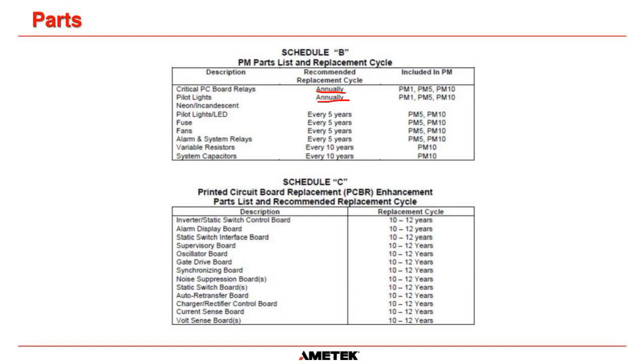Any pilot lights. On our DPPs, we've gone away from pilot lights. So on our oldest systems, we will replace the lamps and the LEDs on an annual basis as well. We replace fuses every 5 years, fans every 5 years, alarm and system relays every 5 years. We replace the relays because the manufacturer recommends the operation period of a relay, due to the coil and the contacts, is around about 5 years.